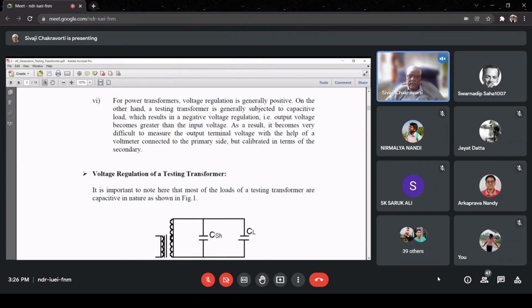Ferranti effect. Exactly the same thing happens in power system when a long transmission line is open circuited. That means only the transmission line shunt capacitance is drawing the current. The same thing happens. That means the receiving end voltage becomes higher than the sending end voltage. Exactly same thing happens here. So power transformers, whereas they supply the load, and our power system load is typically lagging power factor load, their voltage regulation is typically positive. That means the full load voltage is lower than the no load voltage. On the other hand, the testing transformer is mainly drawing capacitive current, and therefore the full load voltage is higher than the no load voltage, and as a result, the voltage regulation is negative. That's a very major difference.